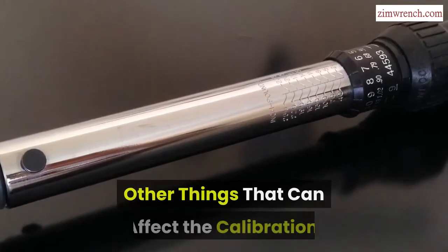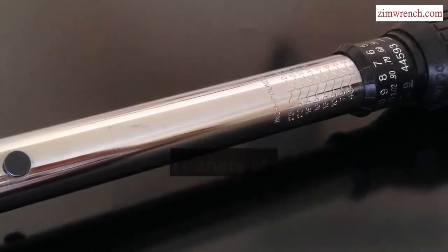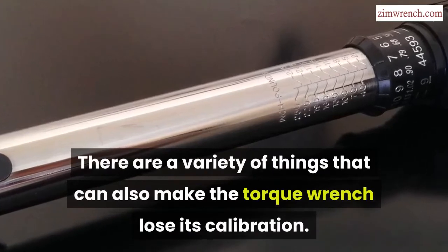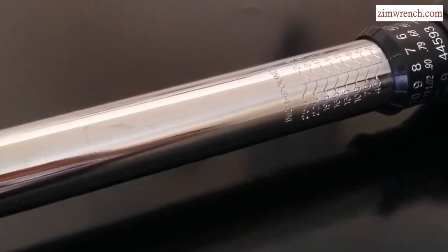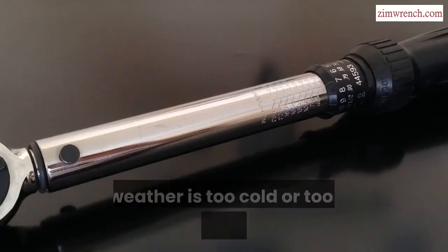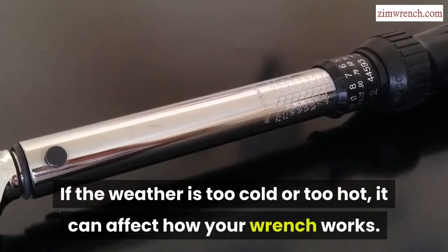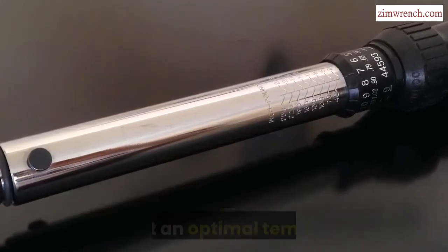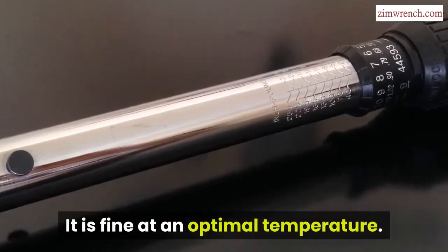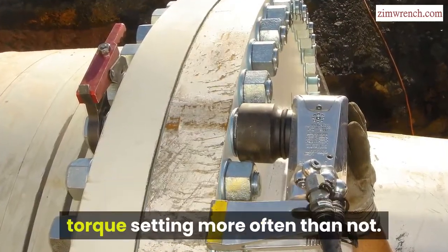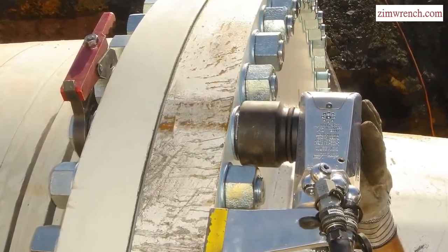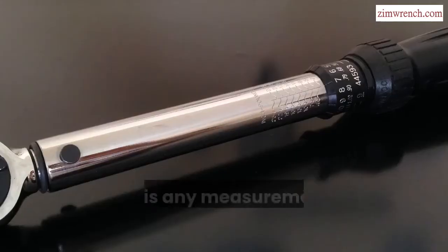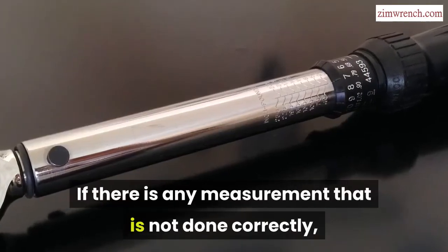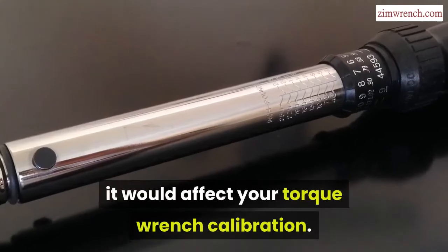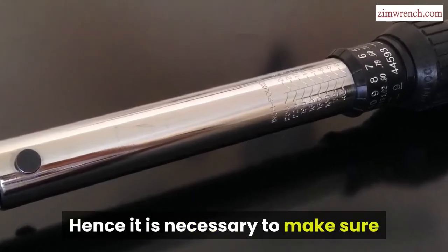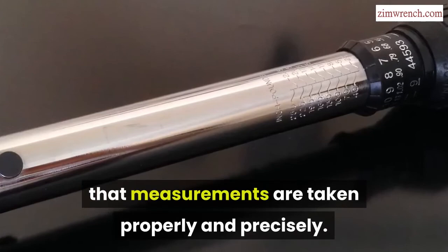Other things that can affect the calibration. There are a variety of things that can also make the torque wrench lose its calibration. Temperature. If the weather is too cold or too hot, it can affect how your wrench works. It is fine at an optimal temperature. If not, you would have to keep adjusting the torque setting more often than not. Incorrect measurement. If any measurement is not done correctly, it would affect your torque wrench calibration. Hence it is necessary to make sure that measurements are taken properly and precisely.